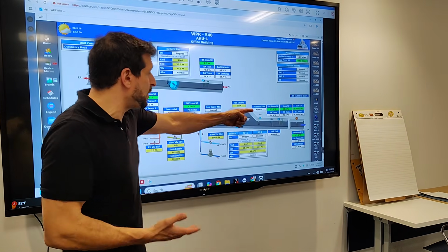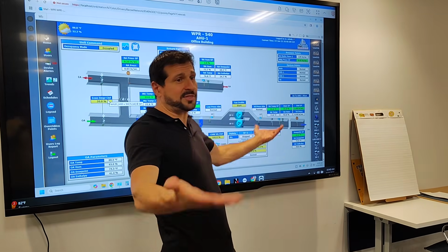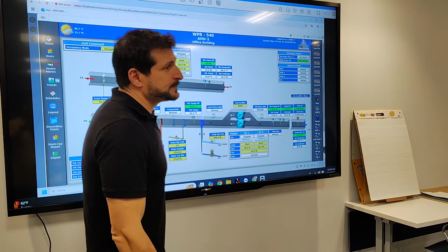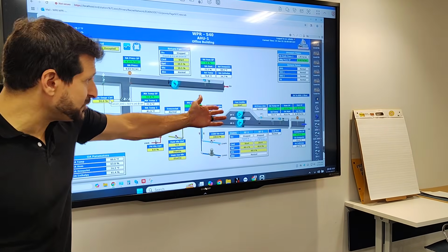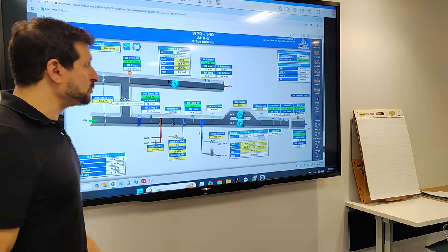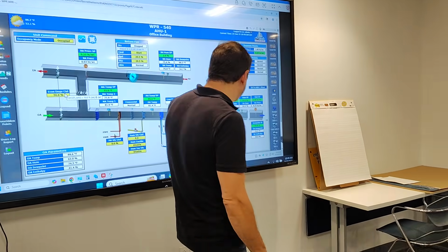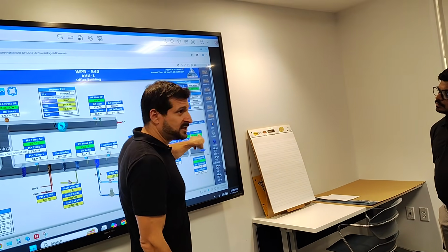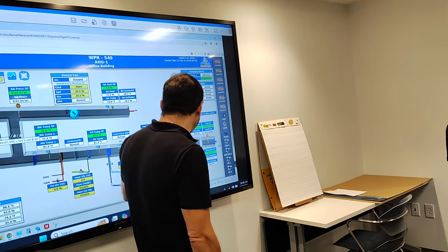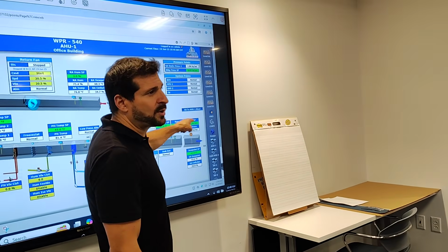You can just tell this thing to go to 1.9 and it's going to sit here at 48.4 for the last 30 minutes. There is no pressure. And you still have only 0.4 inches of pressure. Yep. So right now, what this thing is trying to do is ramp this to get this to equal this. And look how long it's taking to get there. So let's say it does get there. Let's say it works and it gets to 1.9.